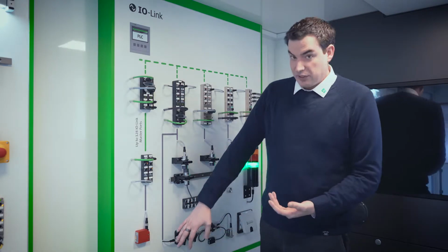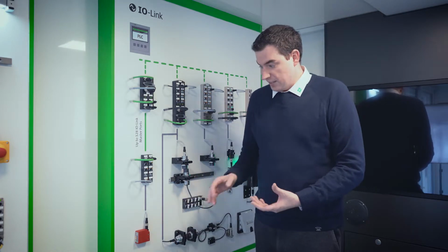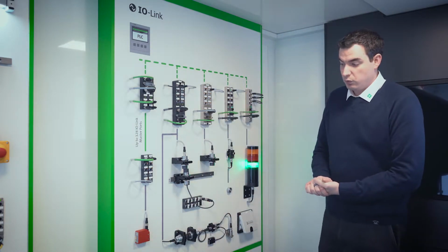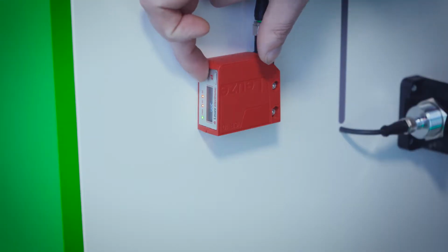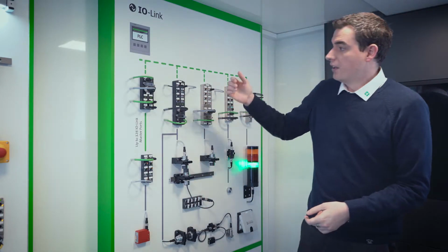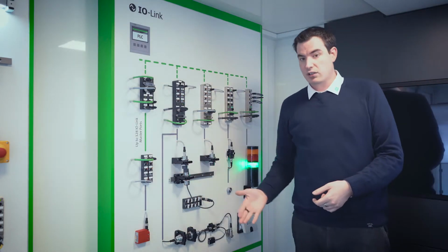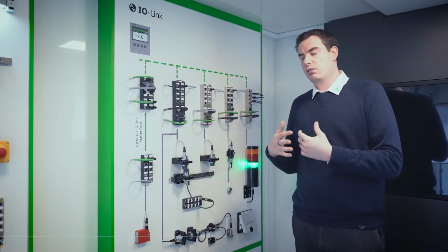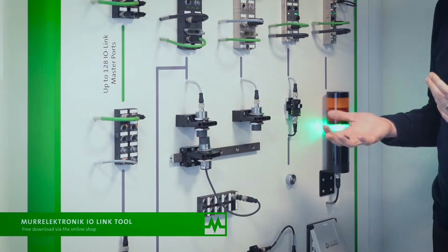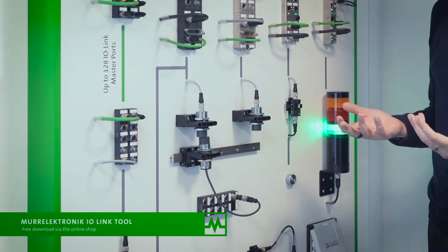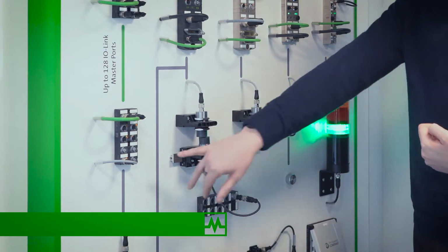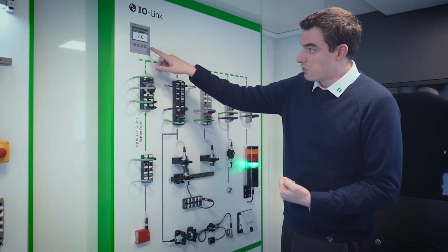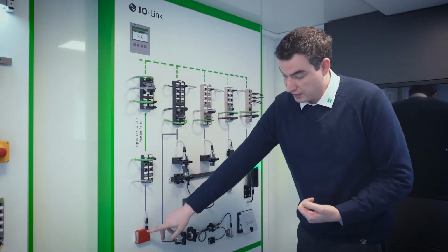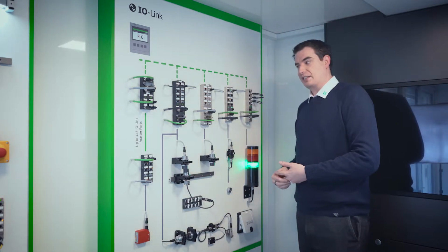With doing that, it also enables you to have remote access to the settings, have remote control within the device, so you can use the buttons. Through an I/O device, you can use a web tool or an Ethernet enabled laptop to be able to communicate to that sensor specifically. You can also write functions within the PLC or the controller to talk down to the I/O to then send and change those settings there.